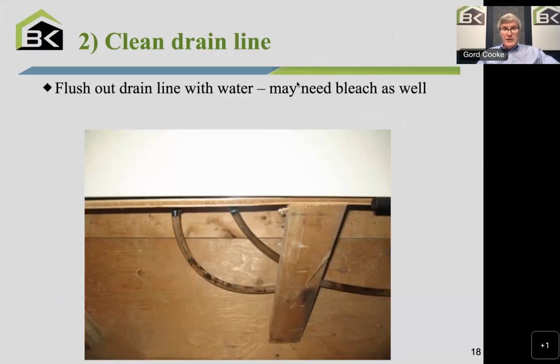There are drains coming off the bottom of HRVs. This is the condensate that, in the wintertime when it's cold outside, is going to be dripping down. And that condensate only runs in the winter. Sometimes, depending on the unit, you might not see much condensation at all, but often there is, and there have been bugs in the unit and so on. So often these drains get plugged. So you want to flush out that drain line with water. A little bucket or a jug of water, and sometimes a little bit of bleach, just if there's a little bit of mold and so on growing in there. So you would just flush that out.